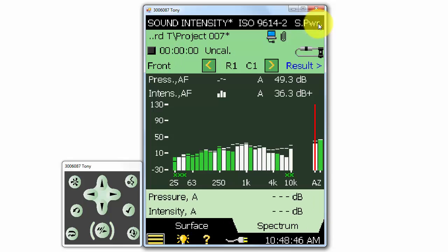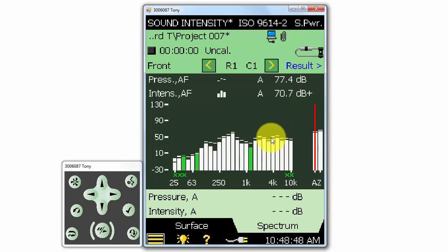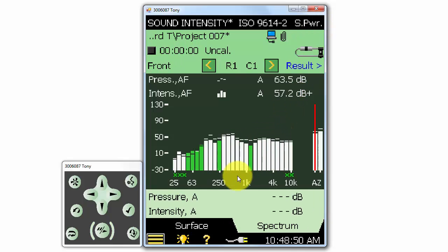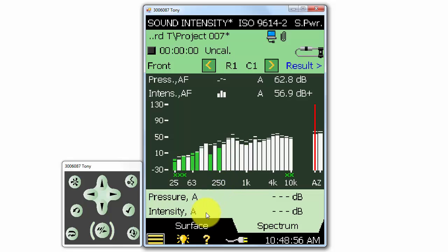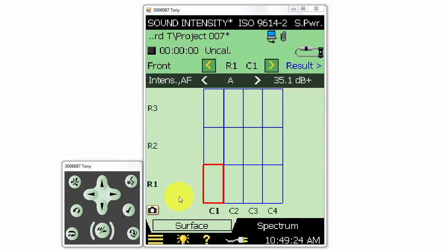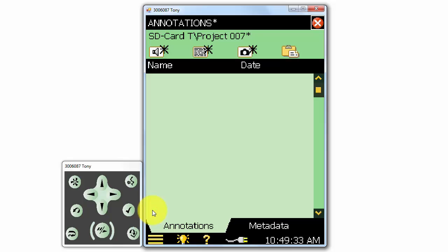Next, we can take a picture of the measurement object with the camera onboard the 2270, so that we can map our defined measurement surface to the object itself visually. We can do that by going to the Surface tab and then clicking on the camera icon to take us to the Annotations menu. In the Annotations menu, we can select an existing picture or click on the camera icon at the top to turn on the camera on the meter to take a new picture.